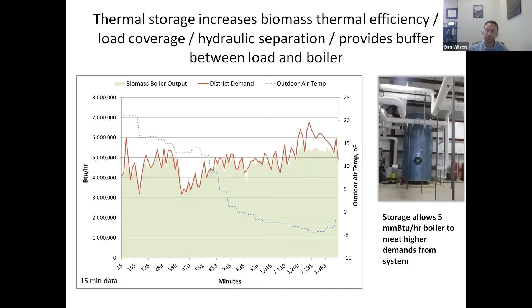The next project I want to talk about is another school, this time in New Hampshire, and this is more of a campus setting. It's got 25 buildings across the campus, and there used to be a steam district heating system that was aging and needing replacement, with 19 boilers across the 25 buildings. They put in a new hot water district heating system, converting over from steam in a lot of cases, and then put in a new central plant to serve that new district energy system.